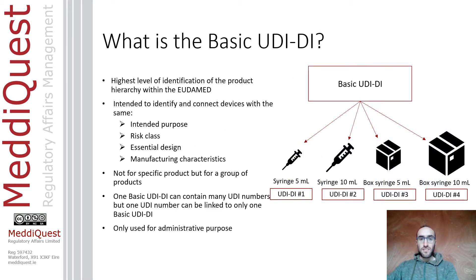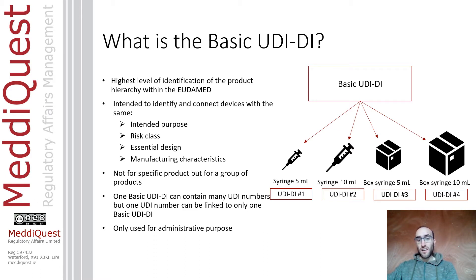The Basic UDI-DI is the highest level of identification of the product hierarchy within EUDAMED. It's intended to identify and connect devices with the same intended purpose, risk class, essential design, and manufacturing characteristics. The Basic UDI-DI is an identification number not for a specific product but for a group of products. Under this Basic UDI-DI you will have one or many UDI-DIs. It has no supply chain value, is invisible to your customers, and is used only for administrative purposes.